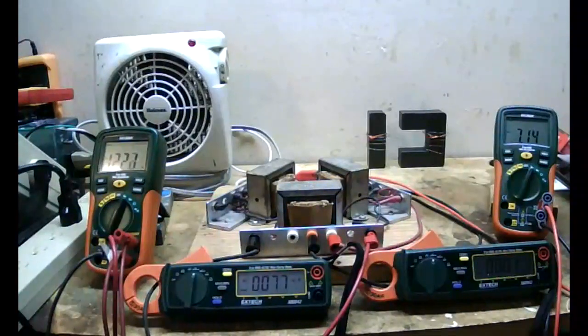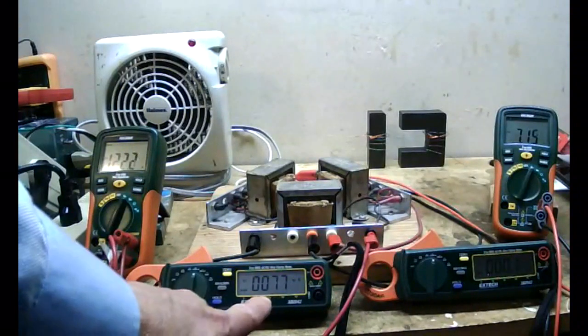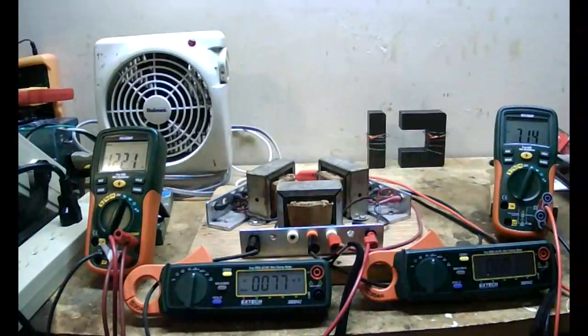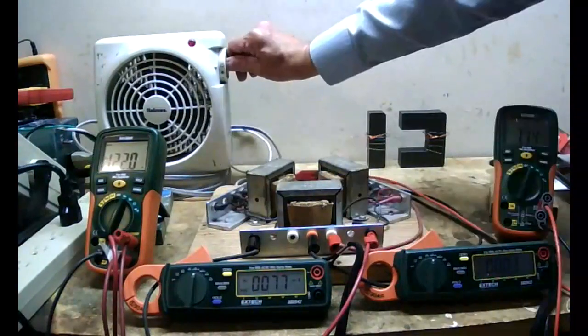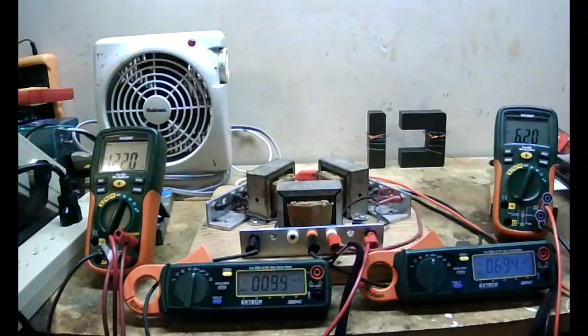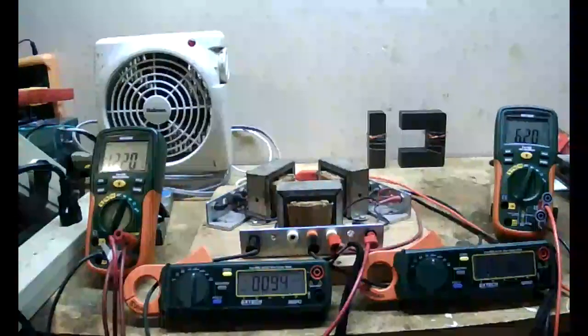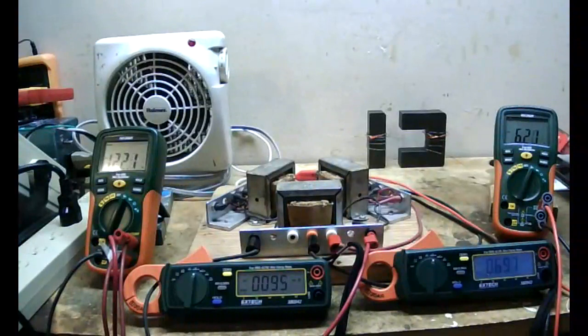There could be some leakage there. Primary current should be zero. If this is an ideal transformer, if there's no current on the secondary, there's no current on the primary. We've got 77 milliamps on the primary. Let's energize the space heater. Now we have about 700 milliamps flowing on the secondary, and we have 95 milliamps flowing on the primary. We should have had 58 milliamps flowing on the primary. Why do we have so much more?